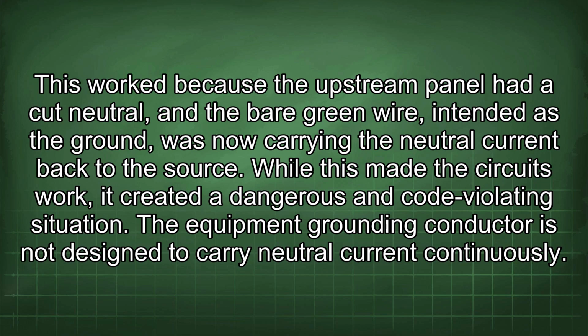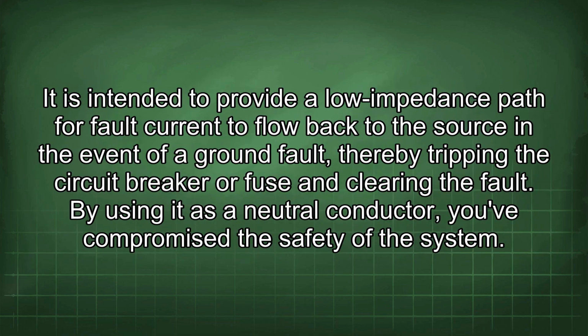While this made the circuits work, it created a dangerous and code-violating situation. The equipment grounding conductor is not designed to carry neutral current continuously. It is intended to provide a low impedance path for fault current to flow back to the source in the event of a ground fault, thereby tripping the circuit breaker or fuse and clearing the fault. By using it as a neutral conductor, you've compromised the safety of the system.